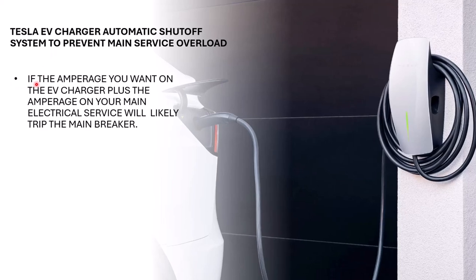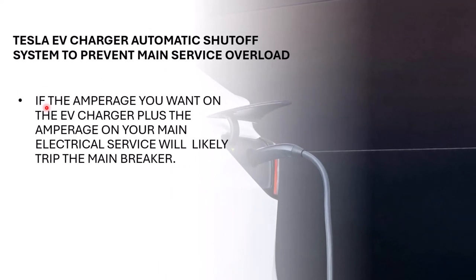So first is if the amperage you want on the EV charger plus the amperage on your main electrical service that it generally sees will likely trip the main breaker. So let's say your current capacity on your electrical service is 80% of the breaker rating, and then you add a Tesla charger. Let's say you want to maximize it to make the charging as quick as possible. So let's say you get a 60 amp charging capacity from the EV charger. And that 60 plus the normal amperage that you normally use in the house exceeds that main breaker. The main breaker will trip and it will basically shut off the power to your entire house. And then you would have to go downstairs and manually trip the breaker back on. And that would be an inconvenience.